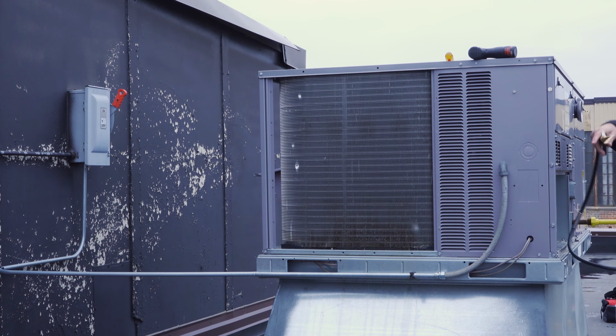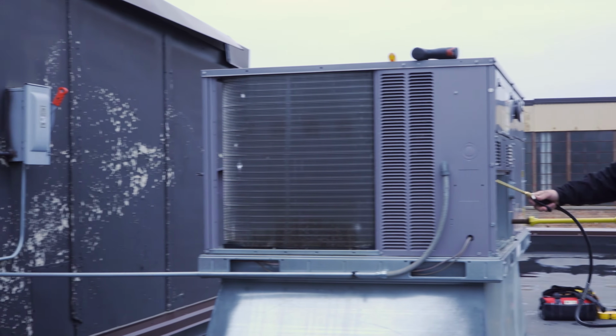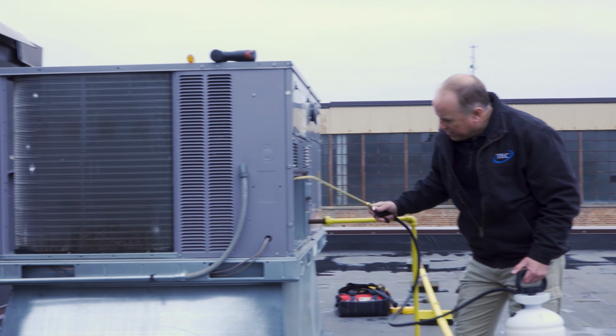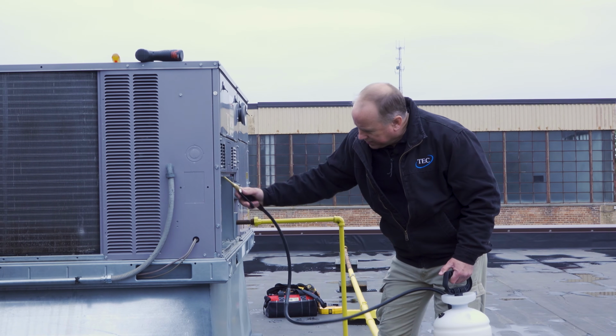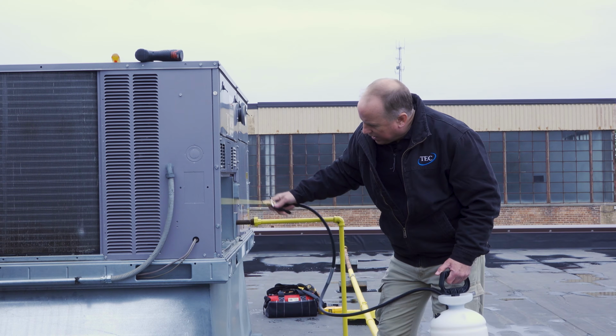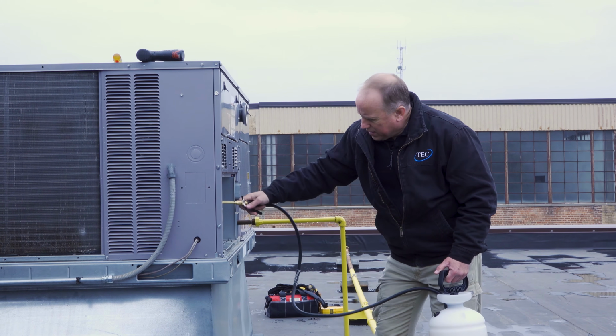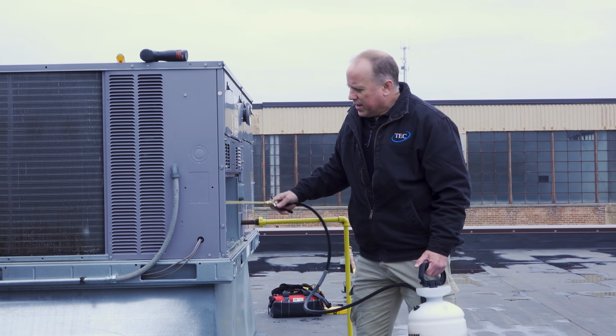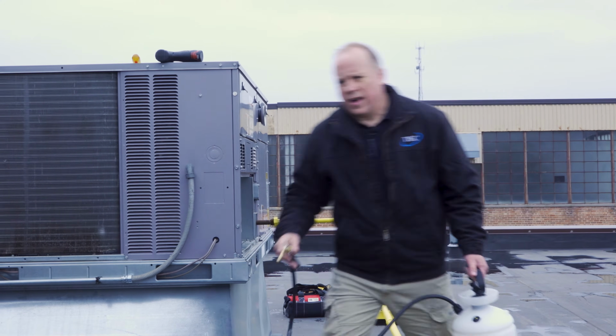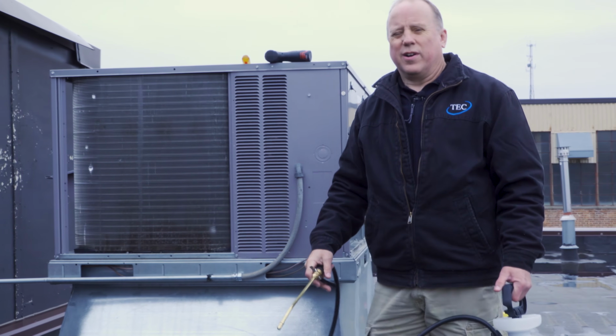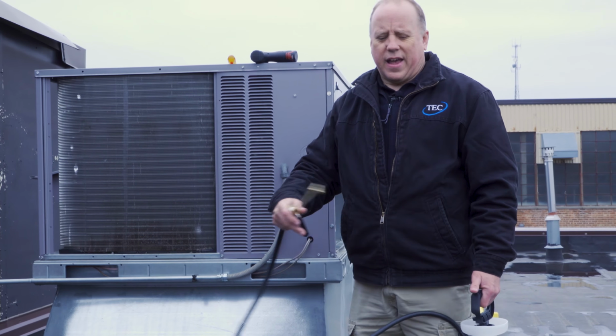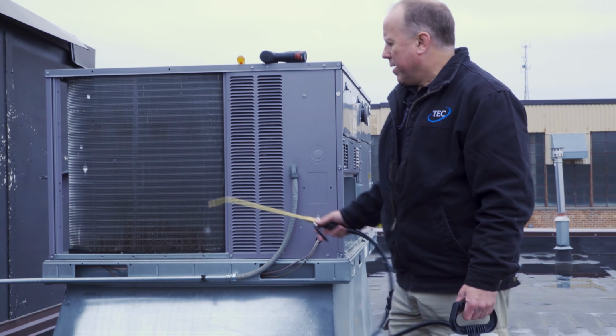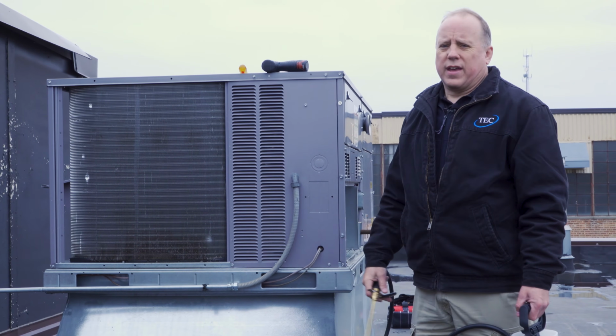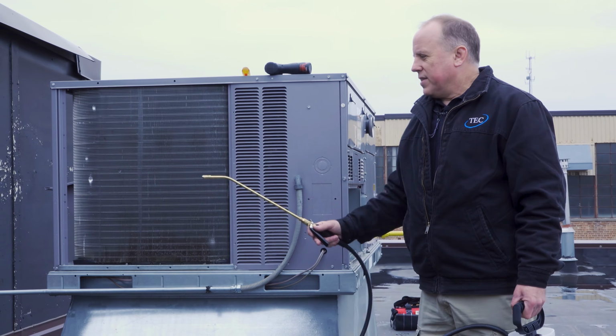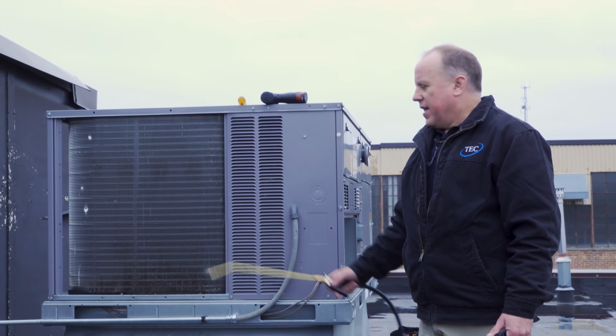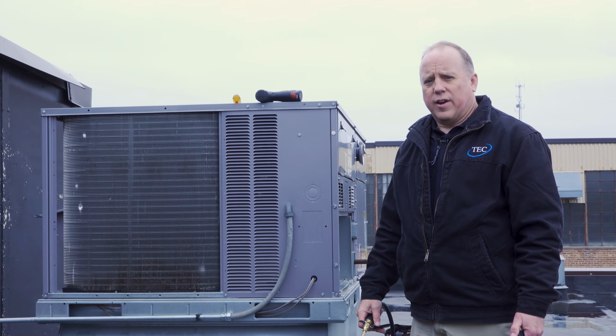This coil actually comes around from the side too, underneath where our control compartment is, so I'm going to get some cleaner on that also. All cleaners are different—some have to sit on the coil longer than others. Again, follow the instructions on the coil cleaner, which will explain the time it may need to sit, foam, or whatever the case is depending on the cleaner. So I'm going to let this sit for a couple minutes, then open the unit up and start cleaning it off.